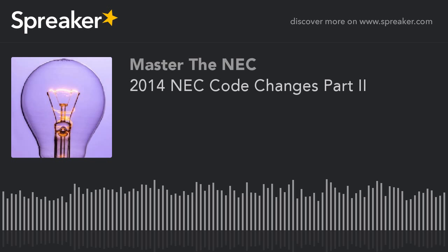All right, 210.17, electric vehicle branch circuits. Let's get something straight. This is not a requirement in the NEC to install a circuit for EV vehicles. What this is saying is that if you do install a circuit for EV vehicles, it has to be a dedicated circuit or a separate branch circuit with no other outlets on it, specifically for the EV application. Outlets installed for the purpose of charging electric vehicles are required to be supplied by a separate branch circuit with no other outlets. So that's its sole purpose.